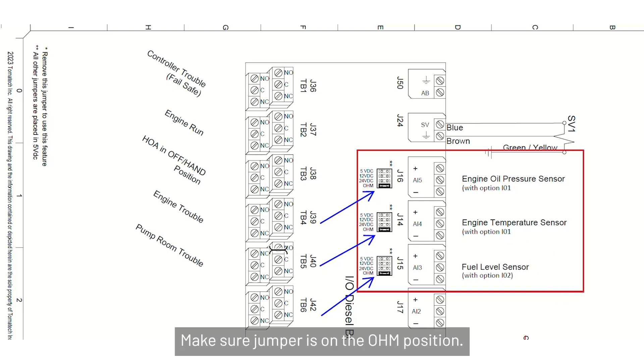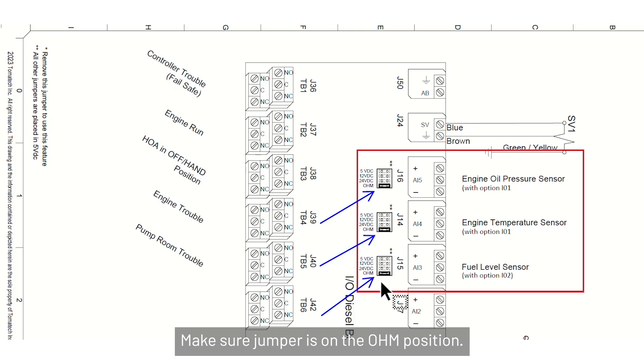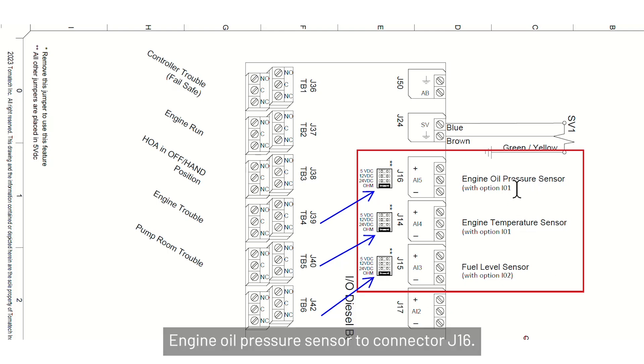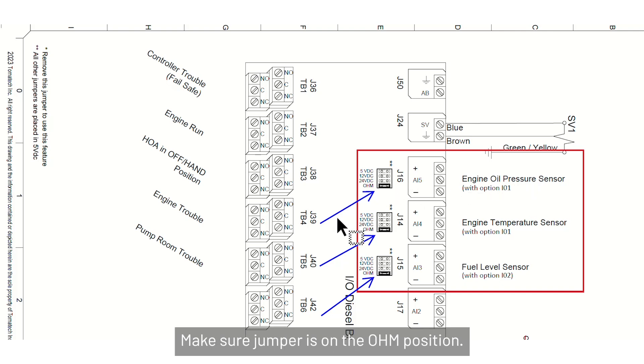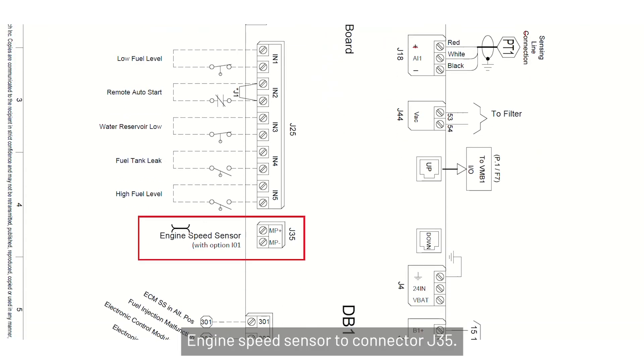Make sure the jumper is on the ohm position. Fuel level sensor (if applicable) to connector J15 — make sure the jumper is on the ohm position. Engine oil pressure sensor to connector J16 — make sure the jumper is on the ohm position. Engine speed sensor to connector J35.